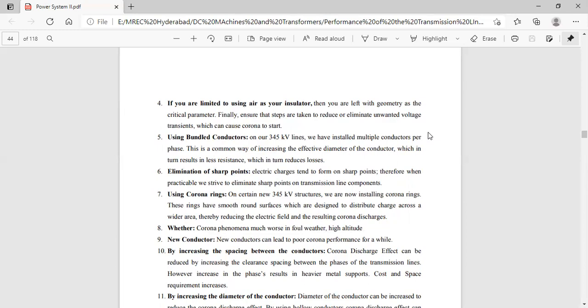The electric charges tend to form on sharp points. Therefore, we strive to eliminate sharp points on transmission line components. Using corona rings: on certain new 345 kilovolt structures, we are now installing corona rings. These rings have smooth, round surfaces which are designed to distribute charge across a wider area, thereby reducing the electric field and the resulting corona discharges.